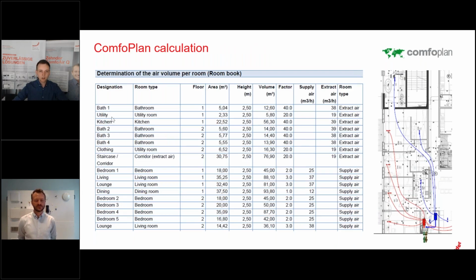This is how the Comfoplan calculation looks like at the end. You can see different rooms divided in extract and supply air rooms with the according areas and the volume flows at the end. So this document, together with a layout, as you can see it on the right-hand side, is given to the service technician who will carry out commissioning and the adjustment of the ventilation system. So until now, I've shown you how we come to these results, what is the theoretical background behind it, and we conclude in this documentation with the calculation of each single room, so that we now can proceed with the technical or practical part.